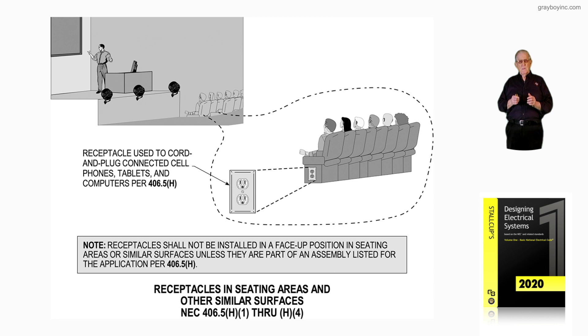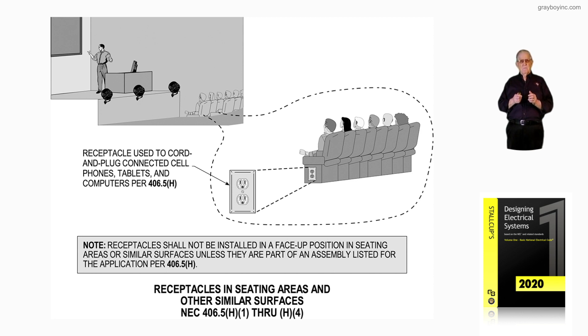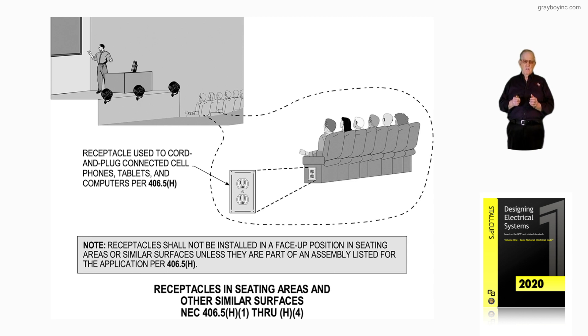The note says when these receptacles are installed, they shall not be installed in a face-up position in the seating area or similar surfaces unless they are part of a listed assembly by the manufacturer and the application does comply with NEC 406.5. Notice the armrest of the individual in the illustration — you couldn't have a receptacle face-up there like you've seen in times past.